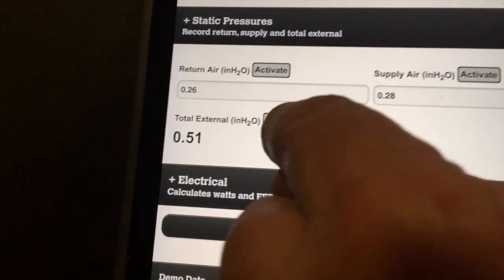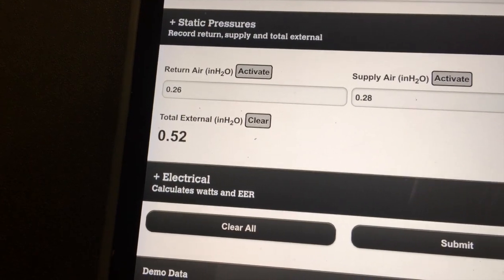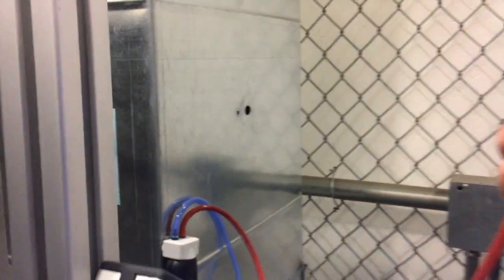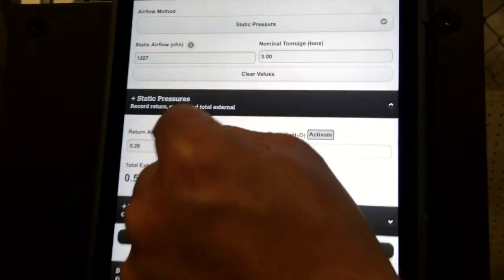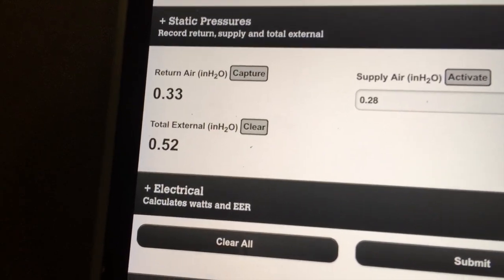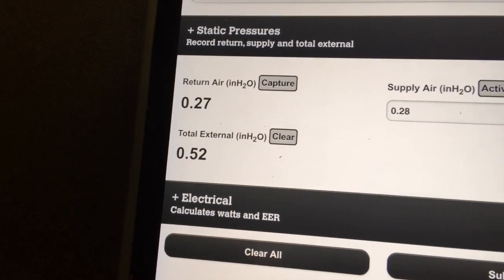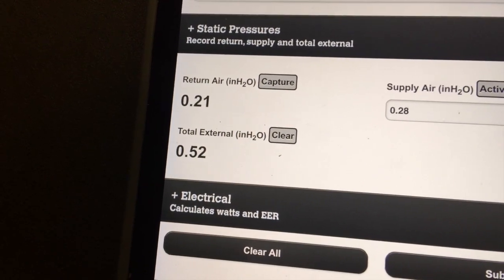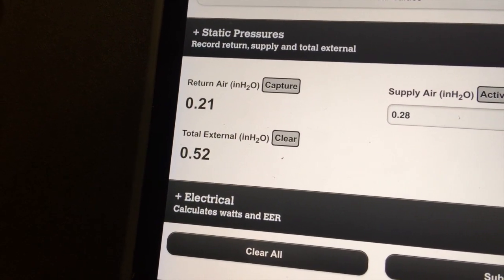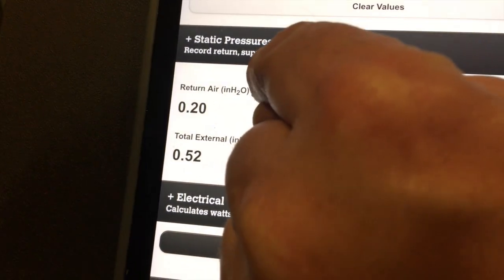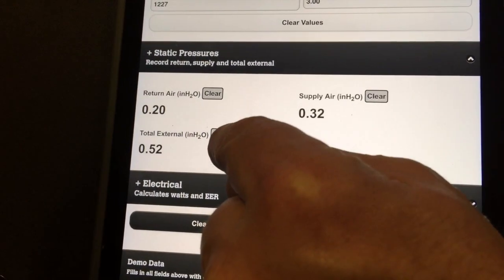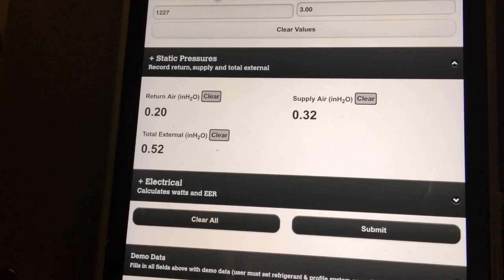So right now you can see I'm reading total external static pressure. I'm going to go ahead and capture that reading, and then I'm going to remove over here my supply air static probe. So now I have no probe in the supply, and I'm going to activate my return, which is what I'm actually reading. You need to give this a few seconds to stabilize. We dampen the reading so it's a little bit more stable. Once you see that the reading's stabilized, right now it's stable, we'll go ahead and hit capture, and it's going to then automatically calculate the supply air by subtracting the return from the total external static. So now we have all of our readings in the iManifold application.